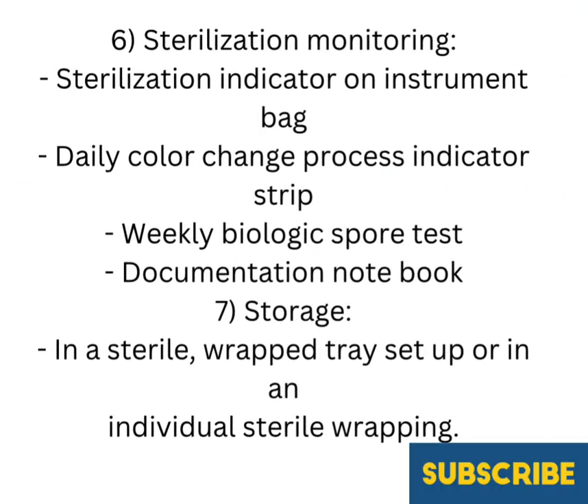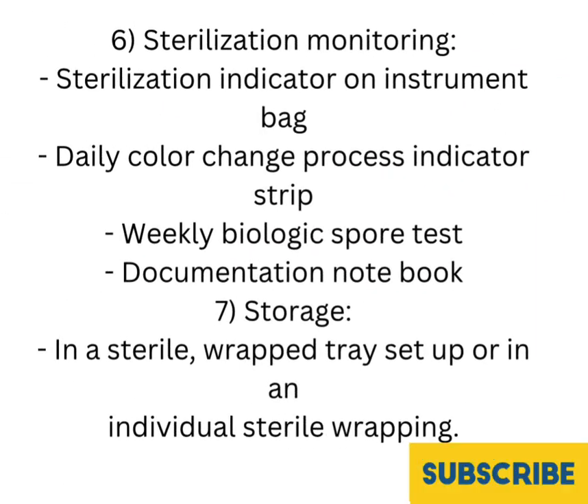6. Sterilization monitoring: sterilization indicator on instrument bag, daily color change process indicator strip, weekly biologic spore test, documentation notebook. 7. Storage: in a sterile, wrapped tray setup or in an individual sterile wrapping.